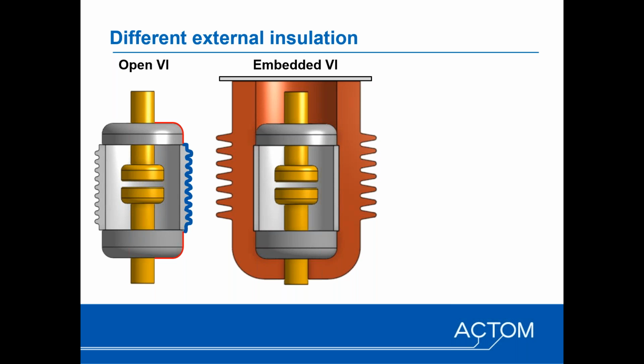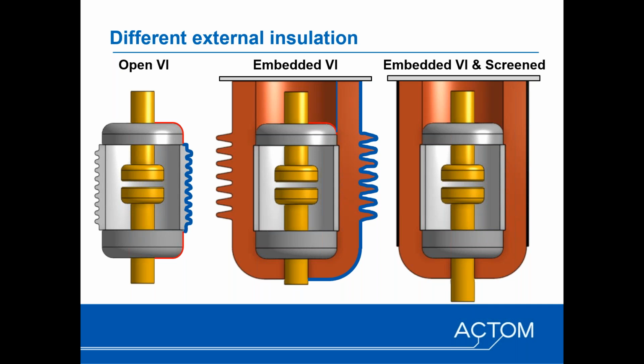In terms of an embedded vacuum interrupter, when you embed the vacuum interrupter into an epoxy resin, you still have an external creepage surface from earth potential to the live potential. You need to make sure that the creepage distance over that external surface is still sufficient to make sure that the leakage current is controlled. In terms of an embedded vacuum interrupter in a screened epoxy surface, your earth screen extends up to the point where typically your cable terminations and bushings are done. So your exposed external creepage extends basically from the end of your earth shield.